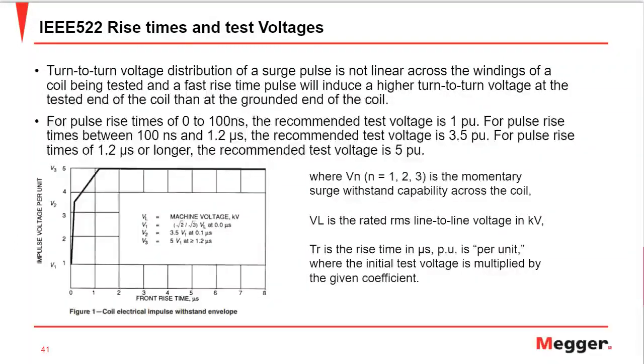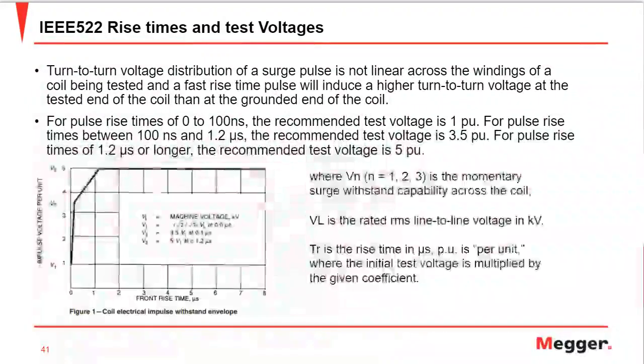So this is an article from IEEE 522, which states why different voltage levels or test voltages should be used at different rise times. So the turn-to-turn voltage distribution of a surge pulse is not linear across the whole winding. And we have seen in the previous slide that the fast rise time pulse will induce higher turn-to-turn voltage at the tested end of the coil than at the ground end of the coil. So a higher turn-to-turn voltage at the tested end of the coil is observed and replicated by sending surge impulses as the pulse moves through the winding. Due to this phenomenon, the uneven distribution of that voltage, IEEE 522 recommends different test voltages for different rise time pulses.